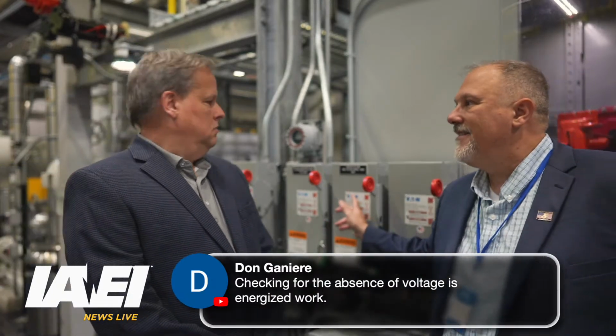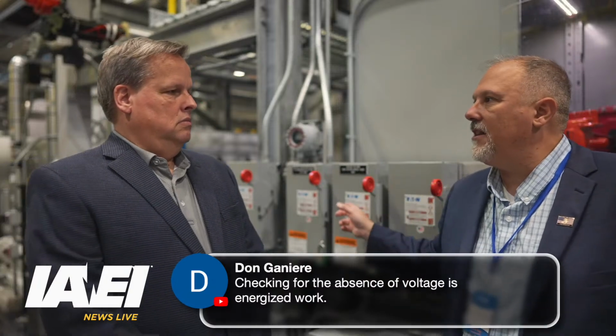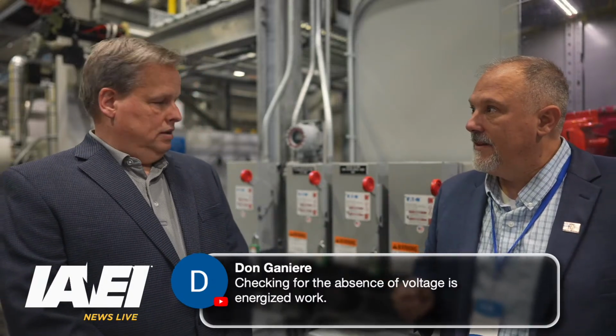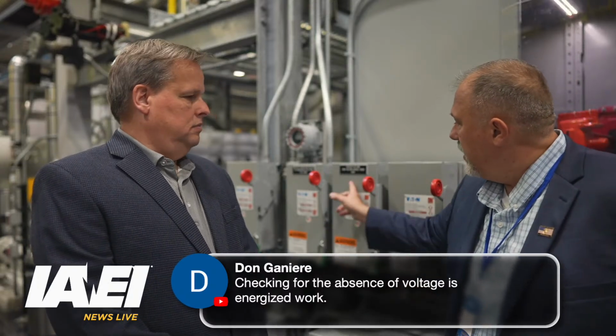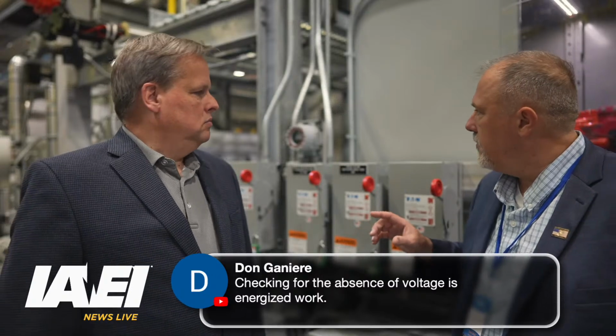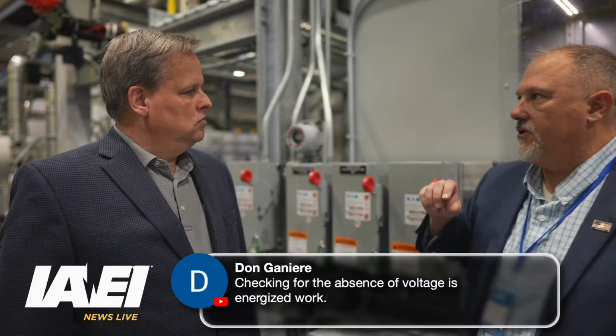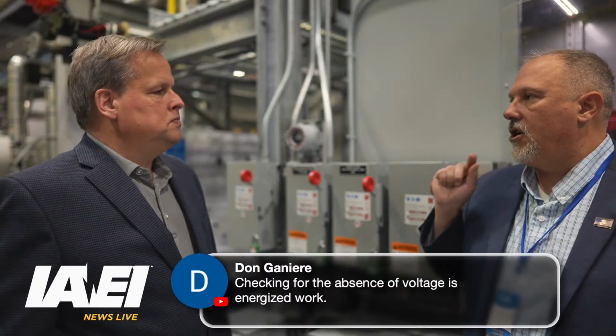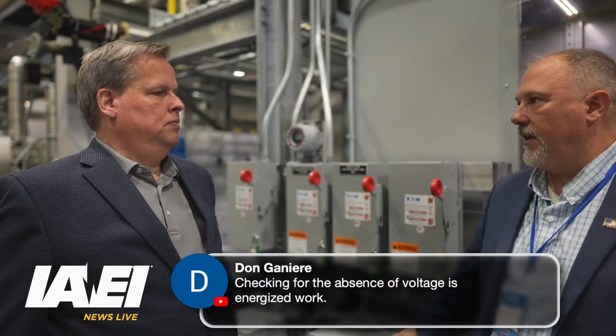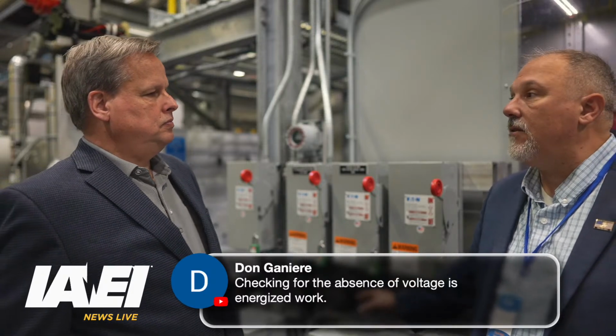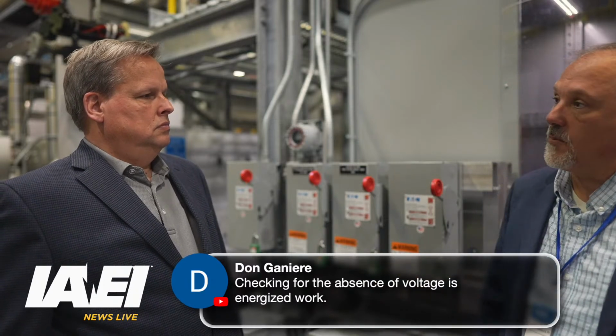I don't have a window here, so I don't have visible indication that those contacts have actually separated. Correct. I could mount absence of voltage indicators on here. I could put a window, and we do have products that have windows. But every one of those increases my confidence that I have truly established an electrically safe work condition, but I still have to treat it as if it's energized until I verify that there's no voltage present. Absolutely. All right, good point, Don.